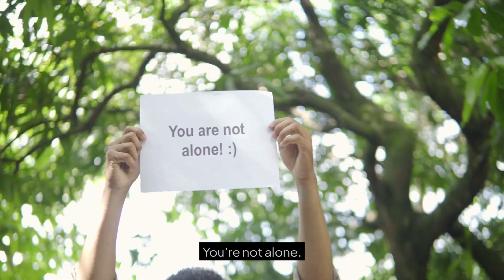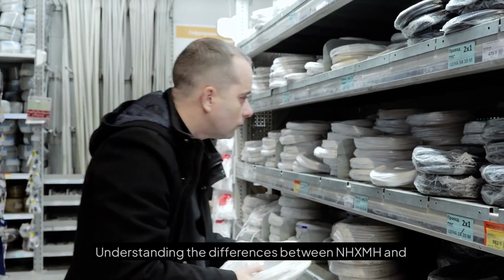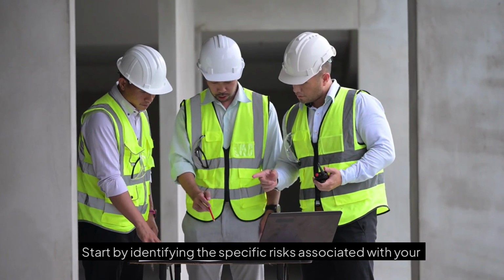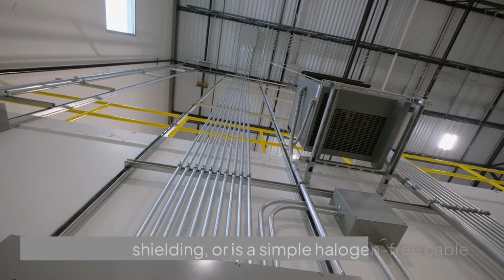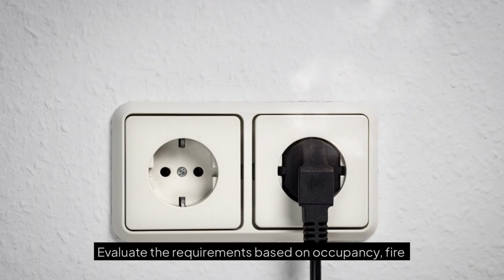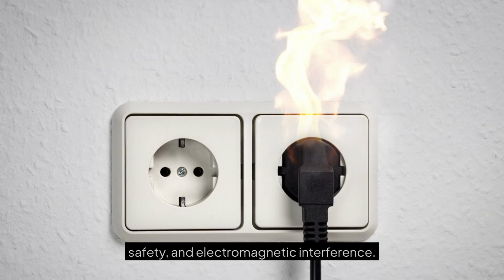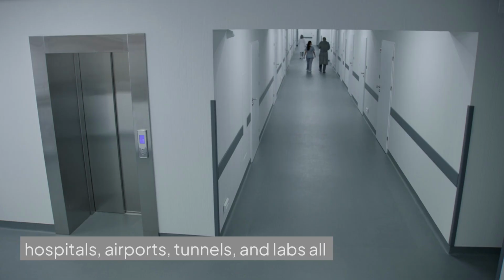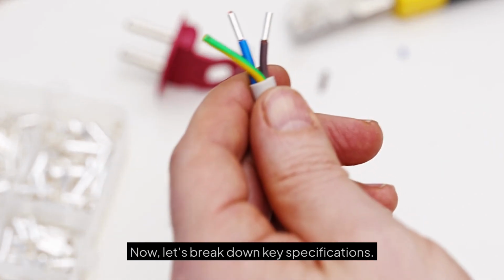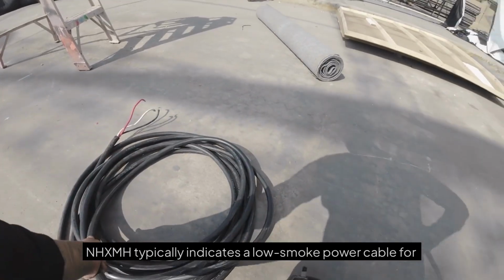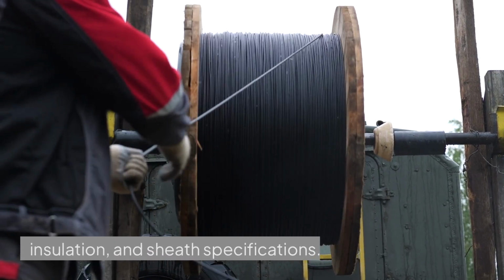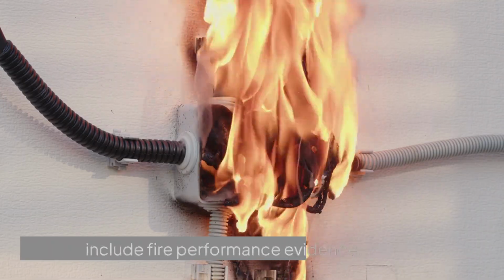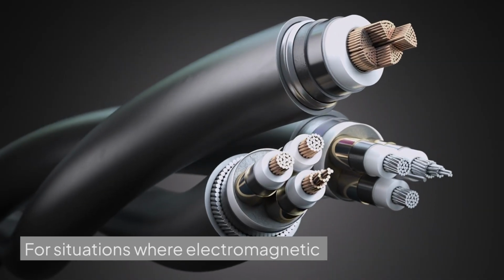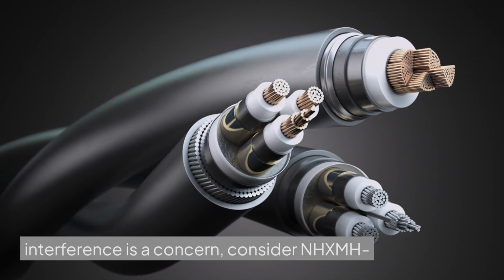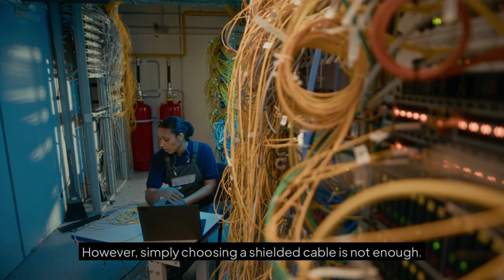Choosing a screened cable without a defined electromagnetic risk can add cost, termination complexity, and installation failure points while leaving the real interference path unresolved. Conversely, omitting screening where power circuits run beside vulnerable equipment can compromise system compatibility. The choice between NHXMH and NHXMH-ST must therefore begin with the circuit, route, and operating environment, not with the assumption that the more complex designation is automatically better.